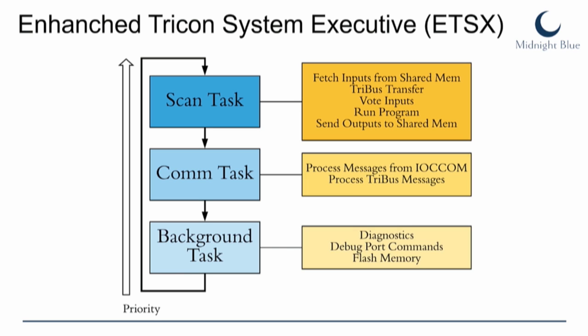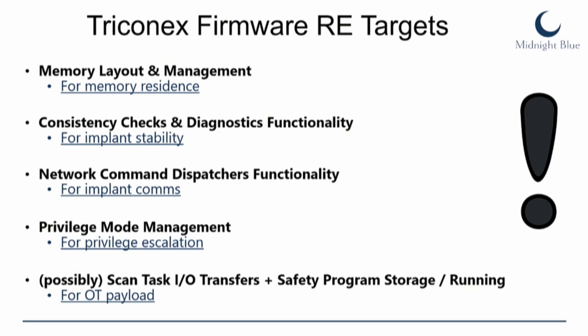Basically, this is what the operating system looks like. You have a scan task, a communications task, and a background task, and we're really only interested in the scan task, which fetches inputs from shared memory, where all the analog and digital I/O gets put. Then we do a triple-bus transfer for voting on consistency, and then we run the actual control logic.